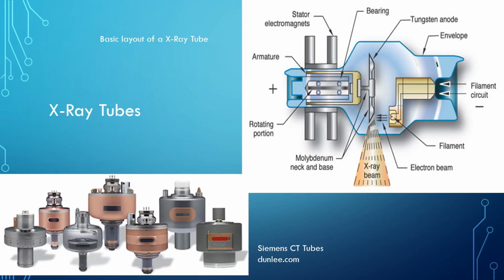And this is a basic layout of X-ray tubes. These examples down here at the bottom are Siemens brand CT tubes. So you have the filament circuit here, and this is where the low voltage supply is applied so that it will get really, really hot. And then that filament, once it gets really hot, boils off or releases those electrons. This is where the focusing cup is, to focus them directly at the anode.